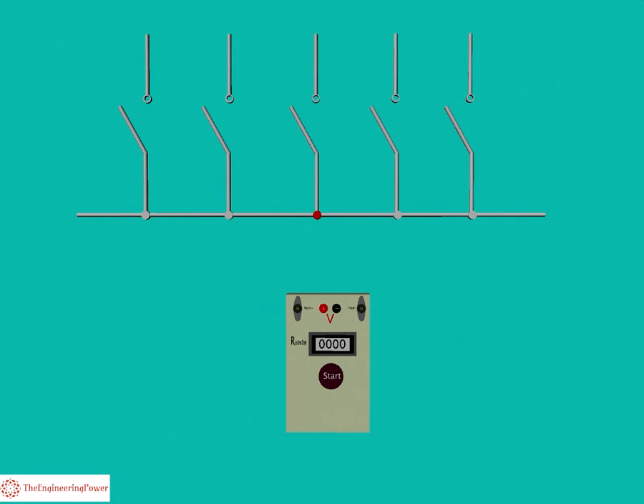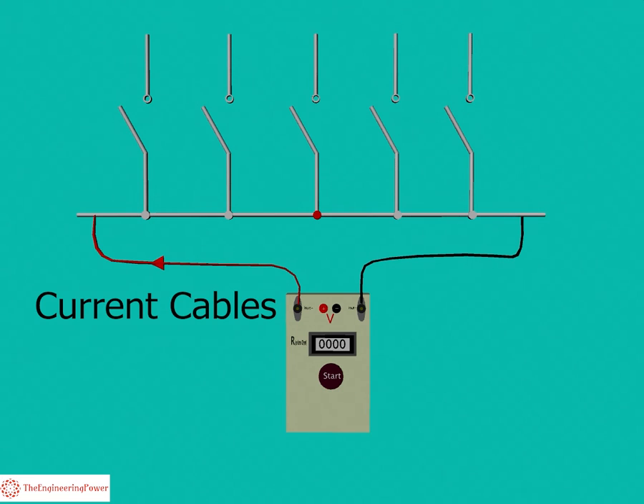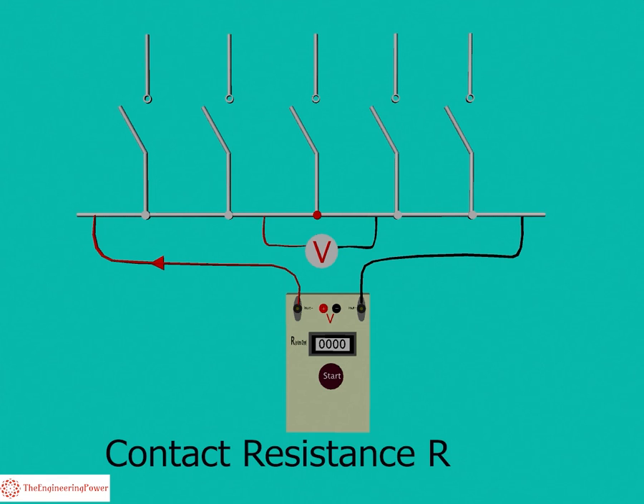We inject current into the bus bar through the current cables of the testing set. After that, we will connect external voltmeter across this specific joint and measure the voltage drop across the joint. Then we will calculate the contact resistance R using Ohm's law, that is R equals V by I.